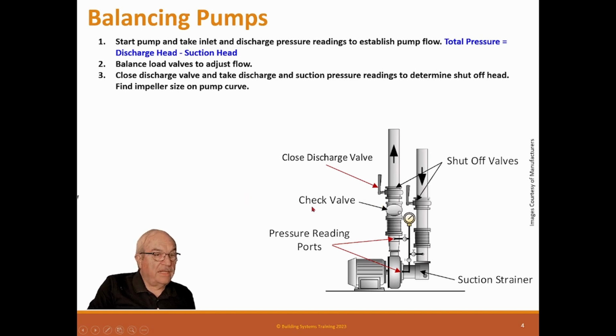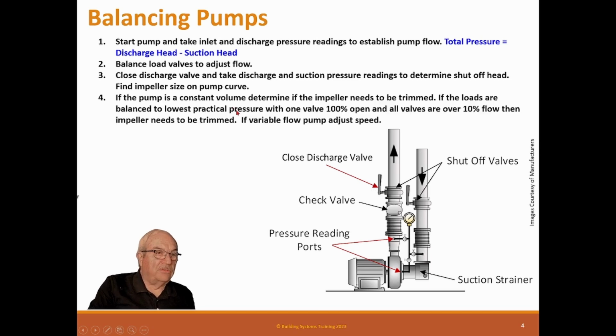Now, you take that data and once you've got that on the curve, and we'll look at this in a second, you can actually determine what size impeller it has, and then you'll calculate what size it needs. And then what they do is they have to remove it from the pump and trim it on a lathe, and then send it back and install it. Now your pump will have the right characteristics to match the load. And the reason we do that is because if you just take this valve and close it off halfway to induce enough head to make this flow correctly, that's costing horsepower, and it'll cost more energy forever. And so that's not the right way to do that.